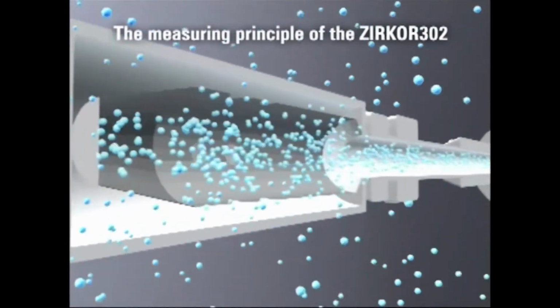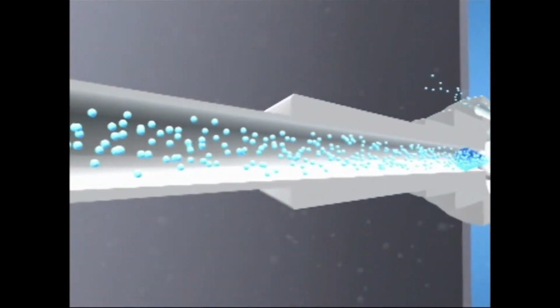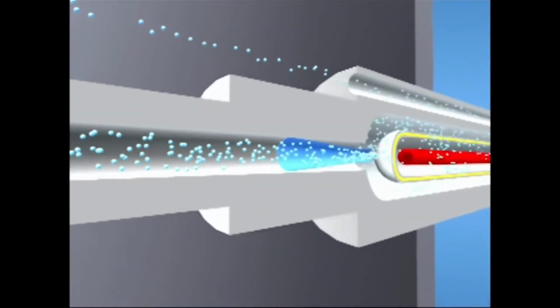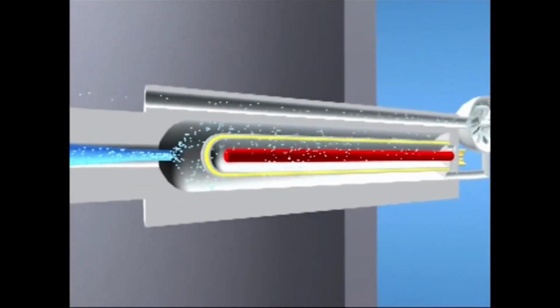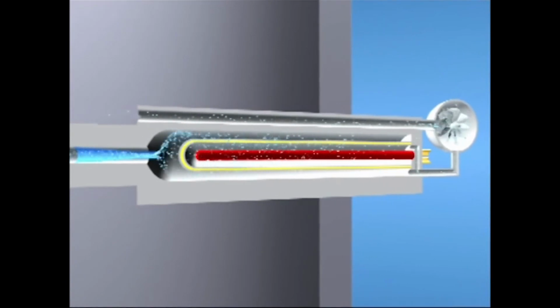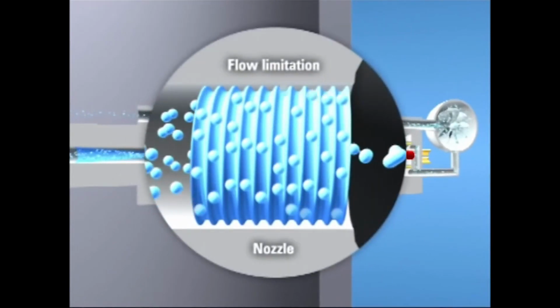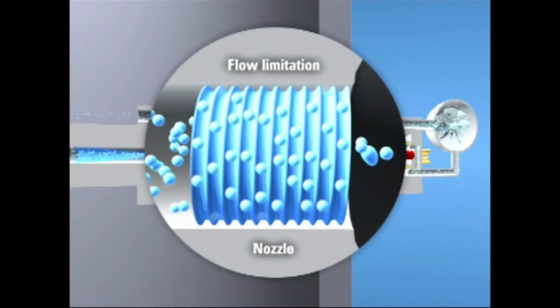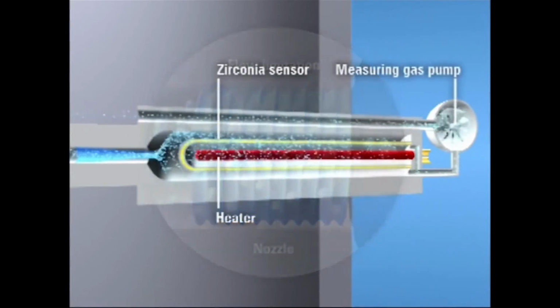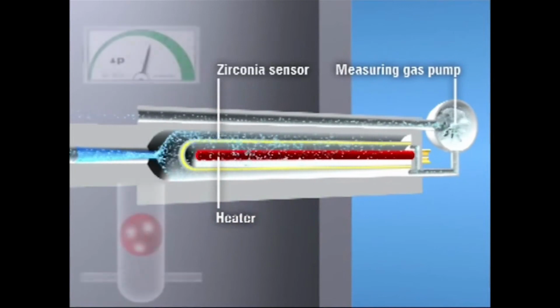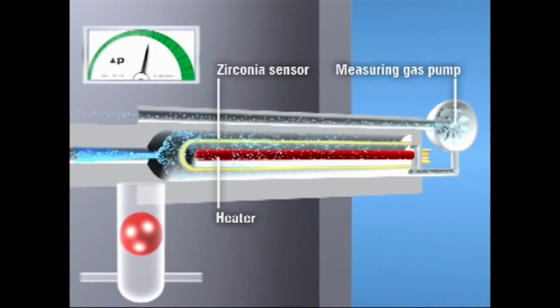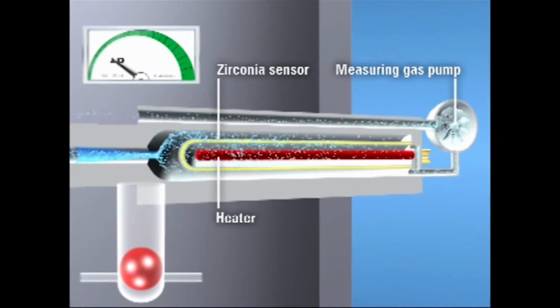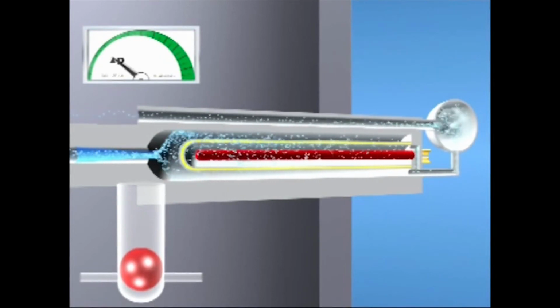The measuring principle behind the ZIRKOR302 will now be explained. A pump, controlled by differential pressure, extracts the measuring gas and conveys it to the measurement cell. The flow rate is defined by a throttle inside the measuring gas extraction system. Using automatic adjustment, the flow rate is set for the sensor current in air, and is close to 500 microamperes, which is equivalent to a flow rate of 0.5 liter measuring gas per hour.